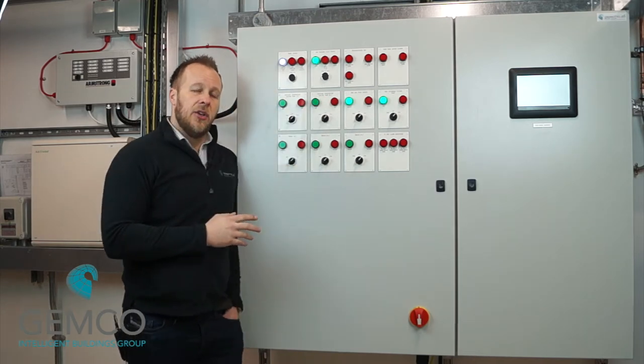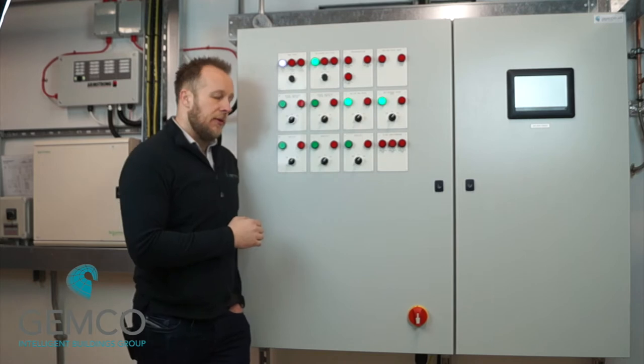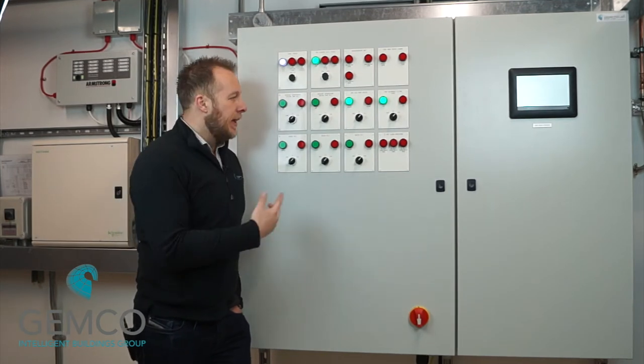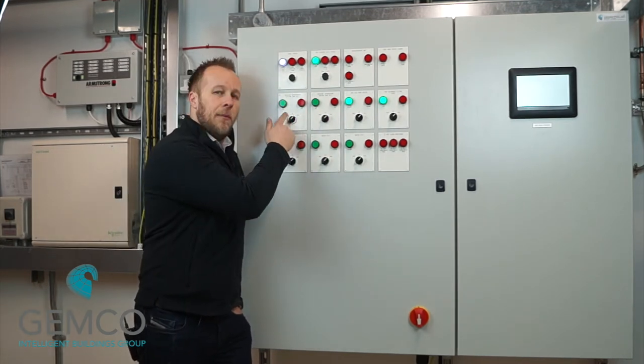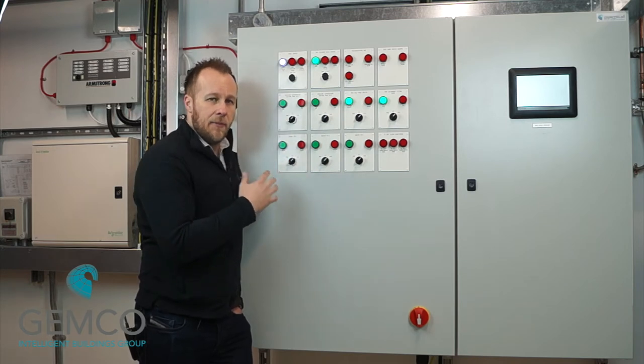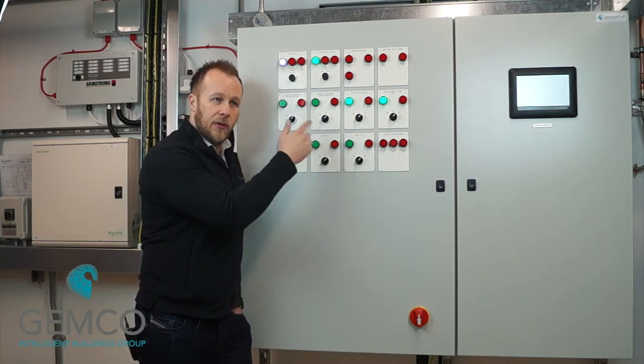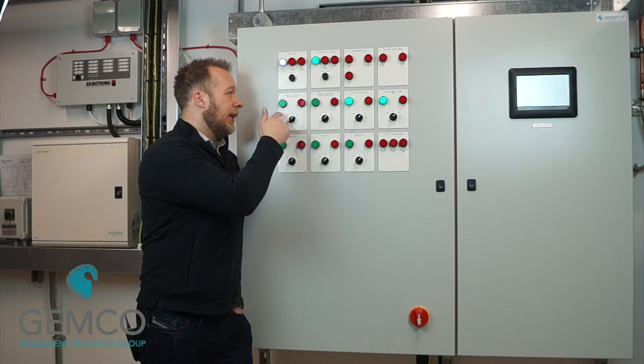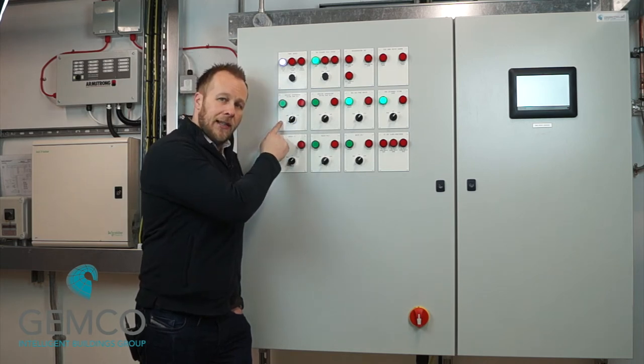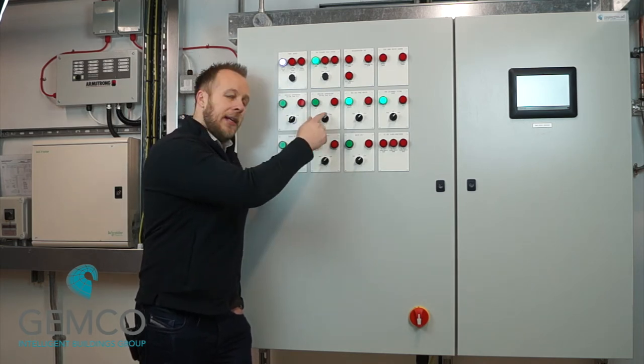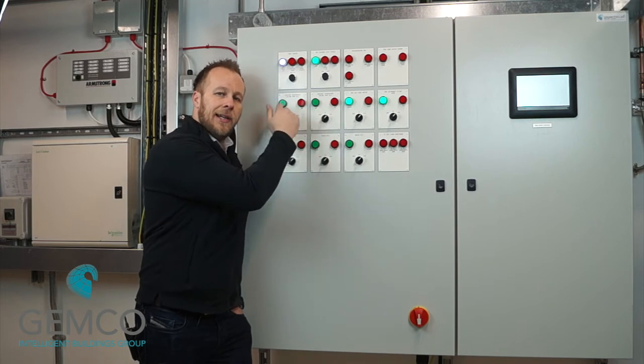So why there's two is, although only one pump should ever be running at any one time, when there's a heating demand, the duty pump will be initiated. So every Monday morning, we change duty. So Monday morning, pump one will be the lead. Next Monday morning, pump two will be the lead, and it will change over on a weekly basis.